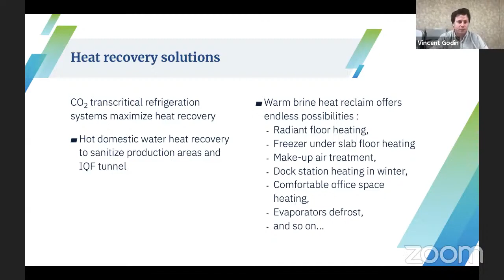A little word on the evaporators. All of the system is pumped CO2 instead of DX. There are significant performance and savings. In phase 3, we also invested in high efficiency fans with VFD so that they don't run at 100% capacity at all times when it's not needed.